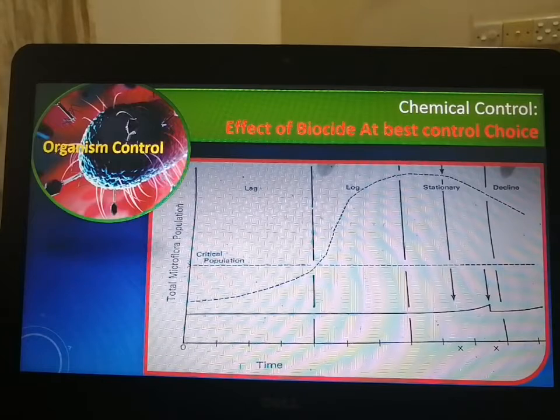So if a system has continuous biocide, then the curve for the bacteria growth remains very strong and stagnant up to a certain number of days at least. So continuous biocide dosing has a very good advantage in controlling microorganism growth below the critical population, or below the lag phase. And if we can really do this kind of control, it means my bacteria number is always below some design number. It may be less than 10 to the power 3, it may be less than 10 to the power 2, or it may be always less than 10 to the power 4.